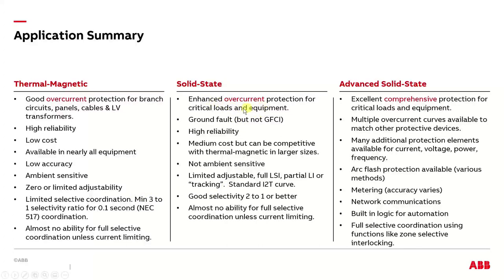The solid state, you get much enhanced overcurrent protection. You get the ability to do ground fault, not GFCI, but ground fault, because GFCI is a branch breaker human safety protection. High reliability. Basically, all the breakers in all these classes have really high reliability anymore, so that's really not an issue. Cost is medium. It's definitely over thermomagnetic in most cases, except when you get into the larger frames, they actually get to be parity, or thermomagnetic's not even available anymore. So the cost has come down significantly, and you could probably get some solid state breakers in places at the same price where you could get thermomagnetic.